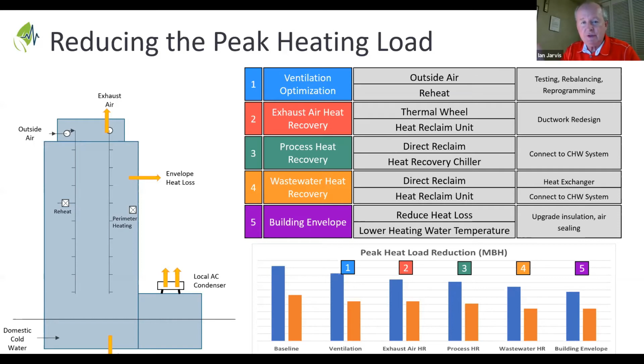So the steps through here that are self-evident, what hospitals are working on now is to optimize the amount of outside air during the wintertime that goes into their ventilation systems to bring that peak down a little bit. Then to look at all of the exhaust air leaving the building and the intakes of air coming in, and look to get thermal wheel applications in to recover that heat. The process heat recovery I touched on a moment ago. So this is picking up all of the heat loads that are being generated within the hospital and thrown away, gathering them together and using them to supply heat.